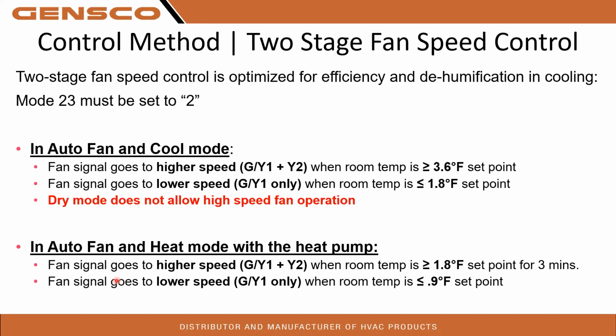How the two-speed fan control works. Again, if two-speed fan control, you have to have mode 23 set to 2. If you're running auto fan in either heating or cool mode, usually we recommend you run high-speed fan because it gives you 100% capacity typically. But if you do have them running in auto in cool mode, how it's going to work for the second speed fan is the room temperature needs to be equal to or greater than 3.6 degrees from set point. So if it's 3.6 degrees or more, it'll kick into the high speed fan. It'll run high speed fan until it gets down to equal to or less than 1.8 degrees from set point. Once it gets down there, it'll switch back over to first stage fan.